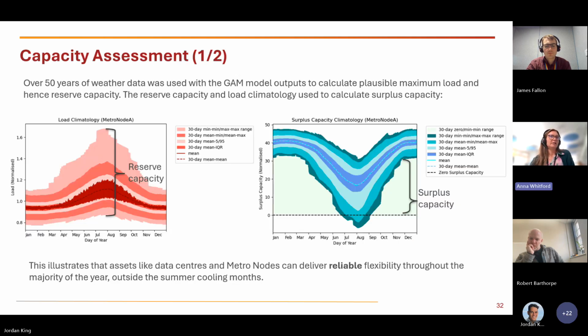To assess the capacity at these sites, we fed 50 years of weather data into the GAM models to create an extended time series, or climatology, of the plausible maximum load, and therefore the reserve capacity available at each site. There's a fixed capacity of reserve power built into each site to meet backup requirements for critical infrastructure, particularly in summer when cooling demand is high. But in winter, when cooling demand is much lower, the requirements for reserve are much lower too, so there's actually surplus capacity at each site. This allows some of that capacity to be used for other purposes — in this case, flexibility.